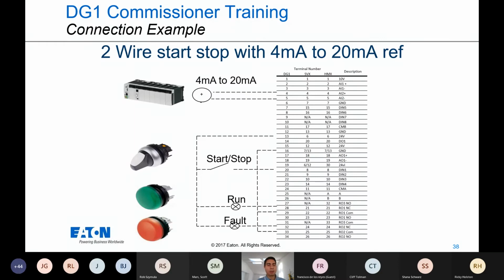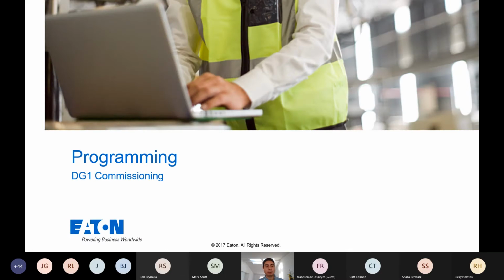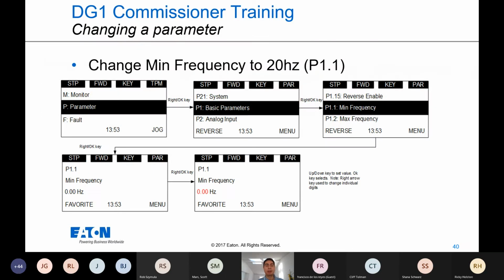An example here that I'm going to show in a second is being able to use a potentiometer or a 4-20mA signal to control your VFD speed. And when you're going through the design procedures, make sure that you have your terminals in the correct locations on the drive. We'll discuss that further, but let's talk briefly about the programming and the commissioning.